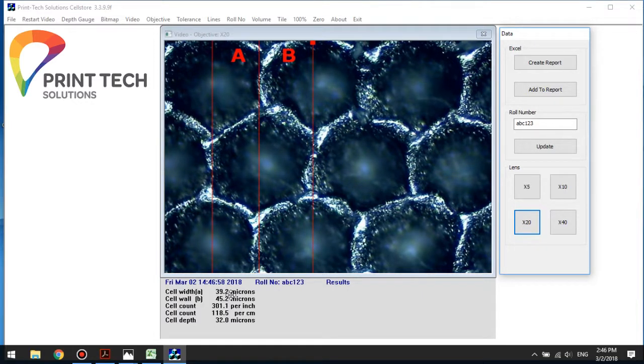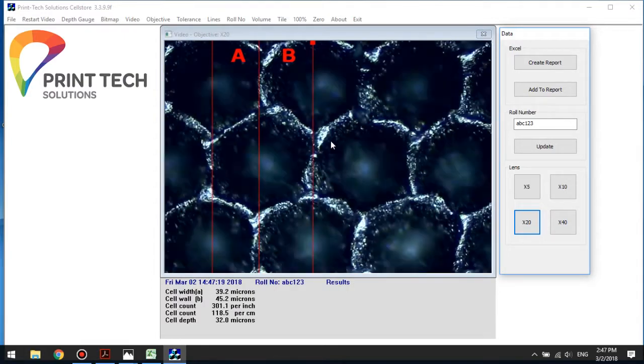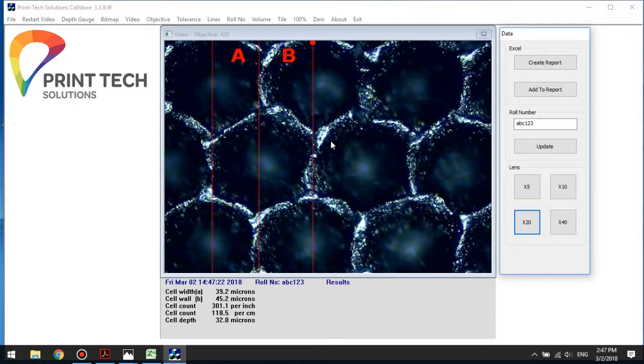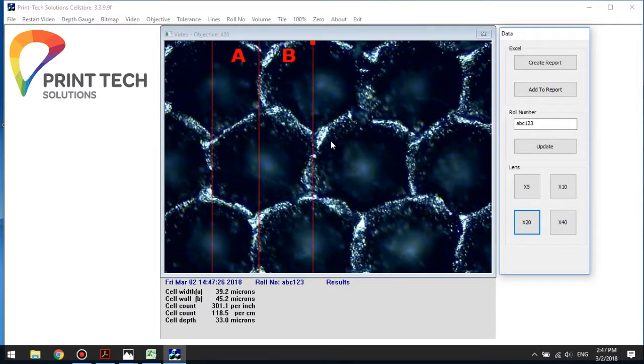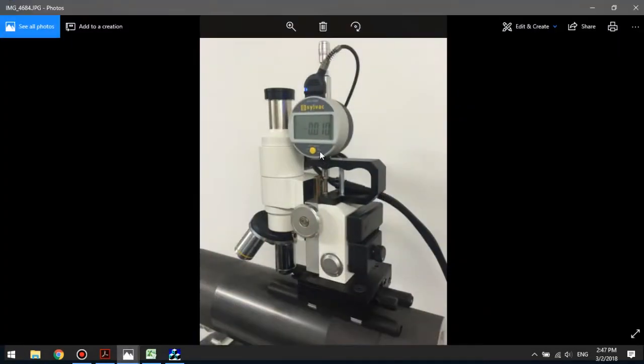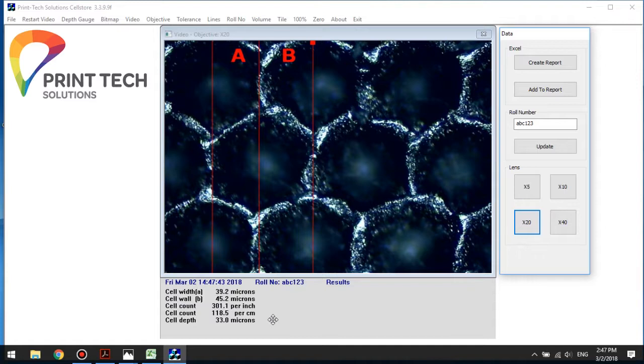The first reading I'm going to take is the depth reading. We do this by differential focus, which means we focus on the top of the cell, then set the depth gauge, then focus down to the bottom of the cell, which will give us our depth reading. I'm looking at this area for the surface of the cell, making sure that I'm focused on that. Now I need to zero the depth gauge by pressing the yellow button on the front of the depth gauge once. At the moment we're reading 33 microns — click that once — and now we have zero microns.